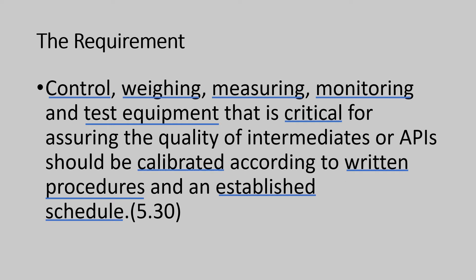There should be a detailed procedure for calibration. The procedure should capture the requirement of calibration of critical equipment, non-critical equipment, internal calibration, external calibration, etc. Each individual equipment should have a separate calibration procedure specific to it. This information has to be linked to the main calibration SOP.